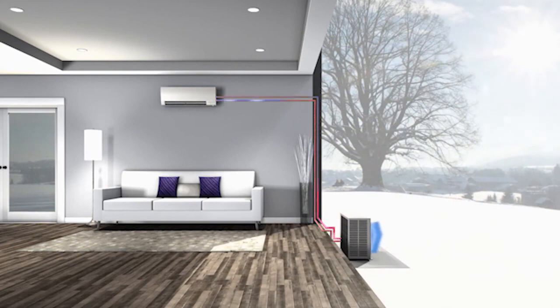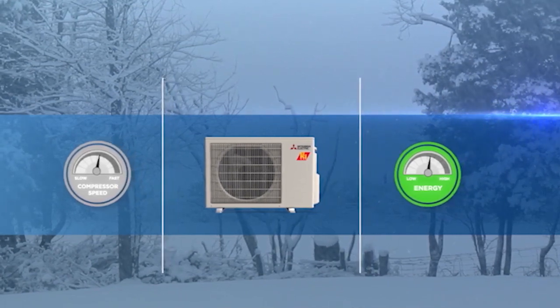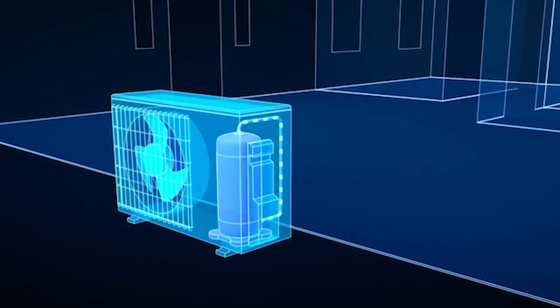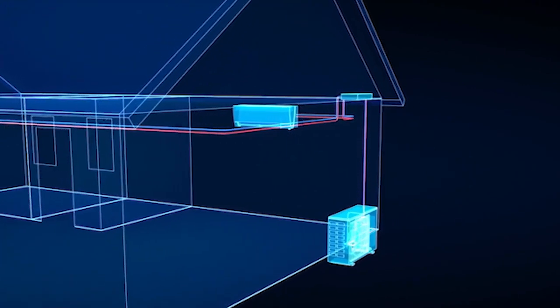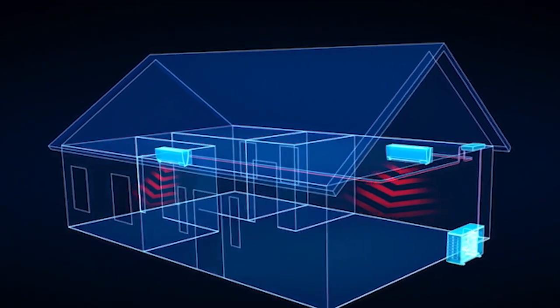The difference in current heat pump technology versus conventional is that it's perfectly able to match those loads — to ramp up and down and condition within a very tight temperature band — giving occupants maximum comfort in any climate, from the hottest day to a cold winter day below zero degrees Fahrenheit. A current state-of-the-art heat pump can do what conventional heat pumps have not: conventional systems are typically one-size-fits-all, one speed or off, and must use electric strip heat below 40 degrees. Those kinds of systems aren't going to contribute to an efficient future, and eliminating strip heat is the first priority as we electrify our economy.